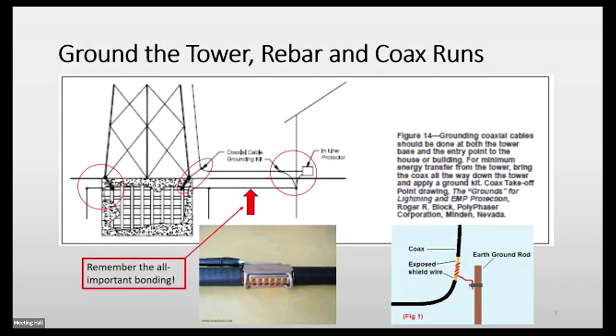Here's another shot from another company. You'll see in this case the coax is bonded - not grounded, bonded - as it leaves the tower. You can see the rebars in the foundation of the tower have been bonded, and the bonding wire into the house or shelter building also has a bond. There are a couple of different mechanisms shown for how that's done, and there are actually kits to do this depending on the type of coaxial cable you're using, to make sure everything stays at the same potential.